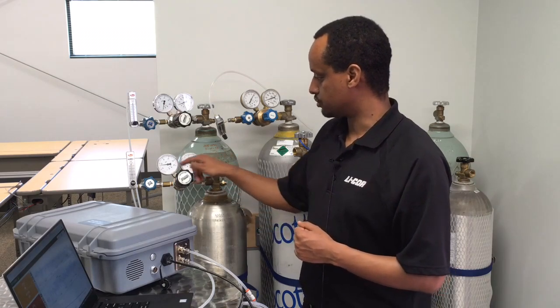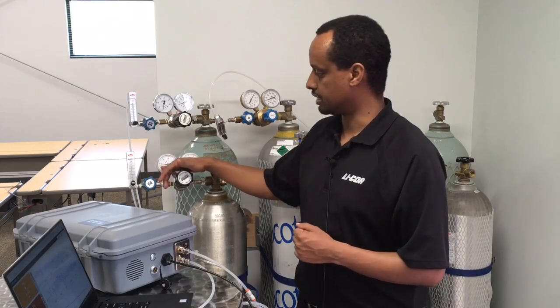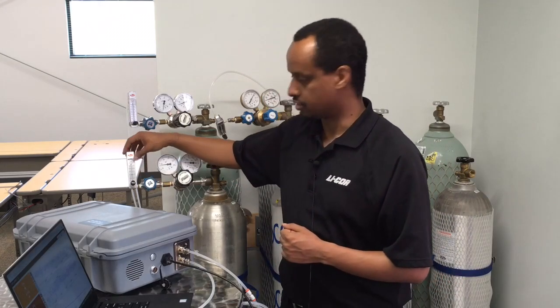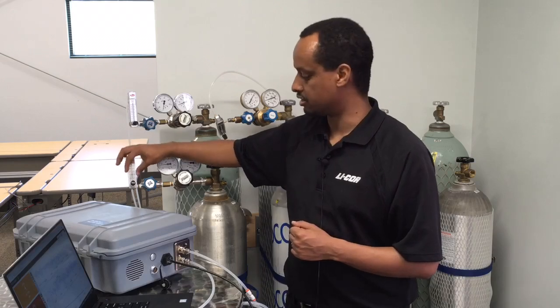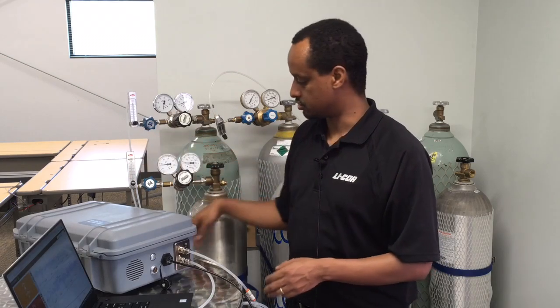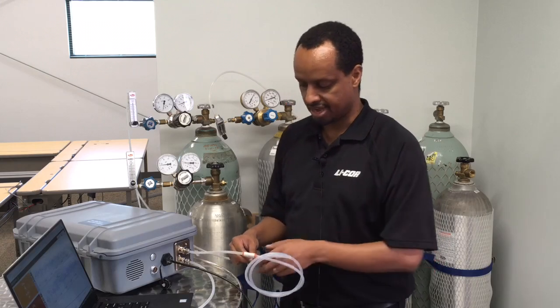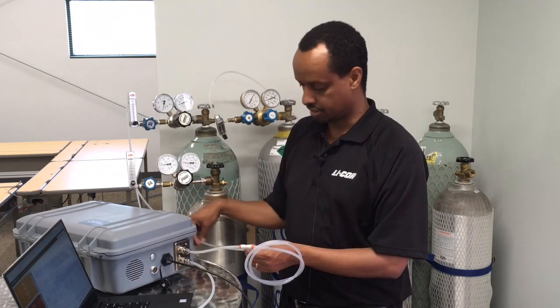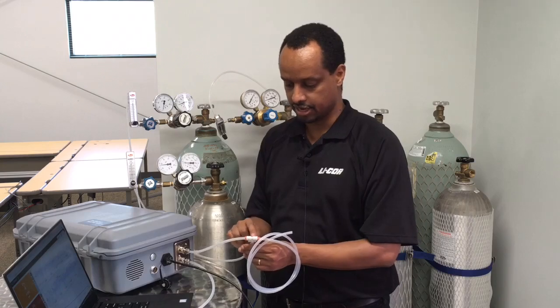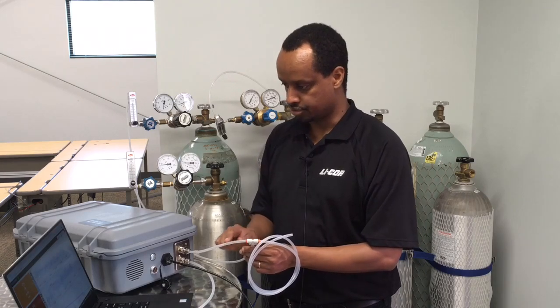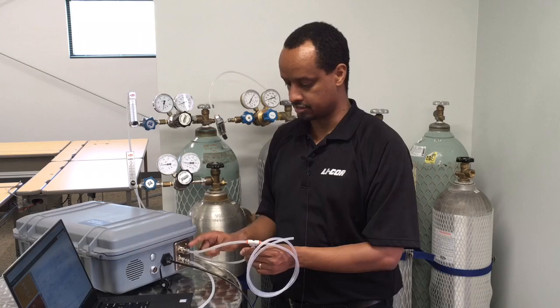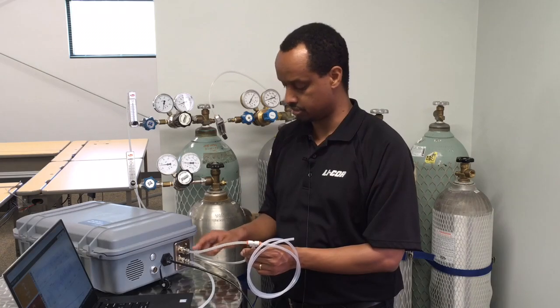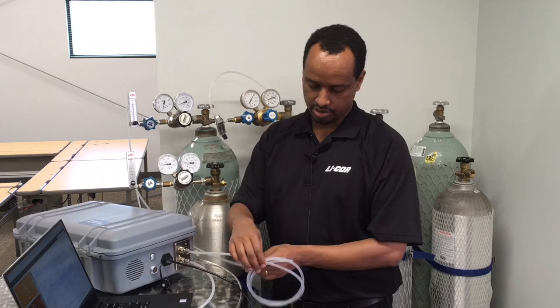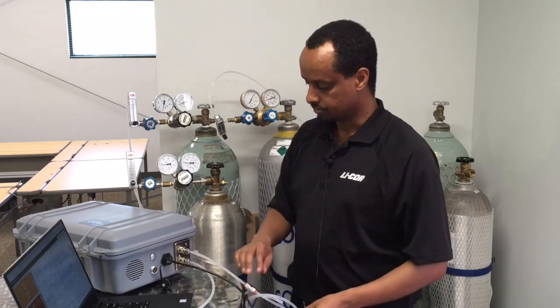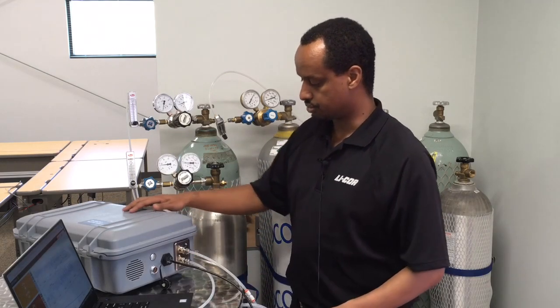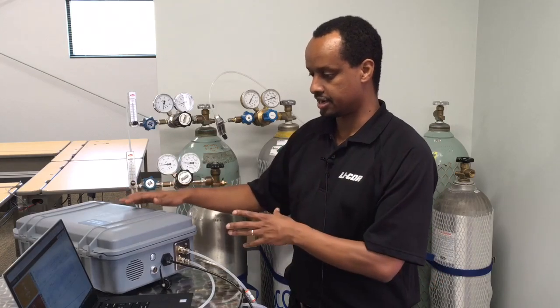So we're using it with a two-stage regulator. I've set it to slightly above ambient, and I've set the flow on the flow indicator to about 1 liter per minute. That's much more than the instrument needs, and I am using a bypass or excess flow setup. So the tank air is going into the leg of this tee fitting here, and I'm pushing the gas into the analyzer. The analyzer is subsampling or sampling what it needs from this flow, and the excess is going out this coil tubing over here.